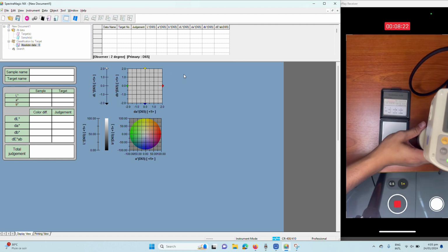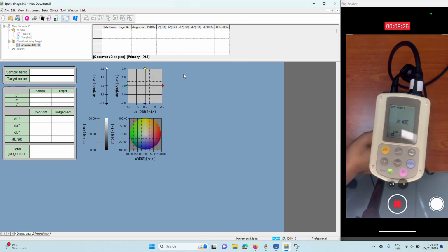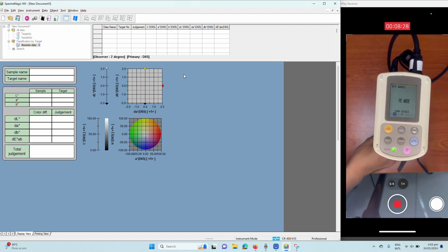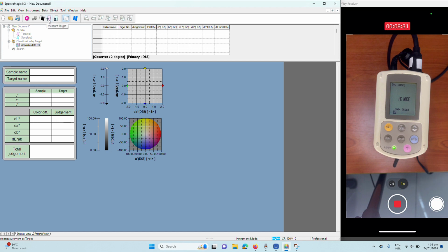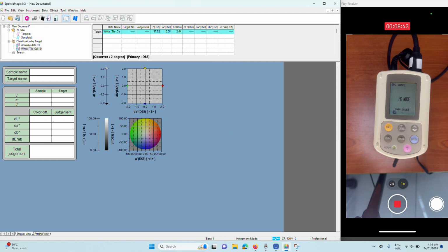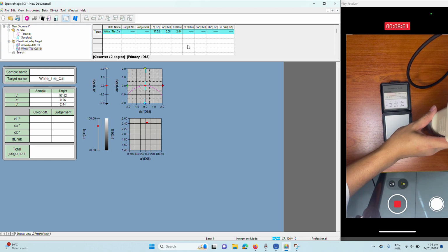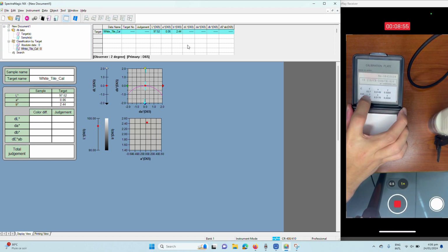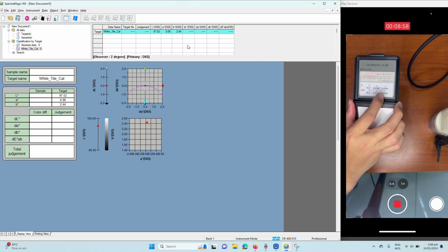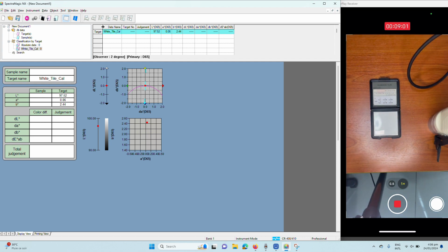So now, how do you know if it is properly calibrated? So what you can do is you can just take the measurements of the white tile. So let me measure it. White tile cal, and then measure it. So now I receive this value. So let's see. So now I can't really tell you if it's calibrated because our calibration is using Y, x, and y. So what can we do here is we can choose different types of data.